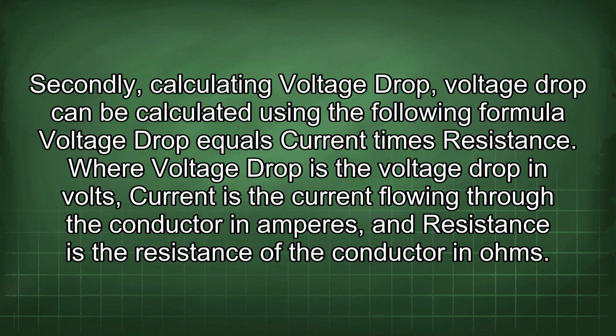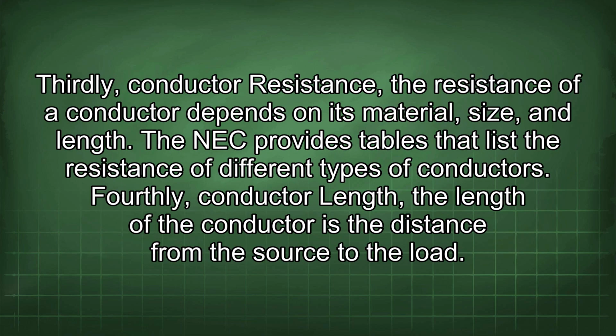Secondly, calculating voltage drop. Voltage drop can be calculated using the following formula: voltage drop equals current times resistance, where voltage drop is the voltage drop in volts, current is the current flowing through the conductor in amperes, and resistance is the resistance of the conductor in ohms. Thirdly, conductor resistance. The resistance of a conductor depends on its material, size, and length. The NEC provides tables that list the resistance of different types of conductors.